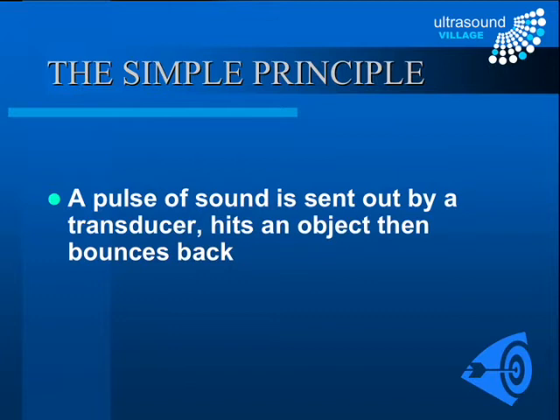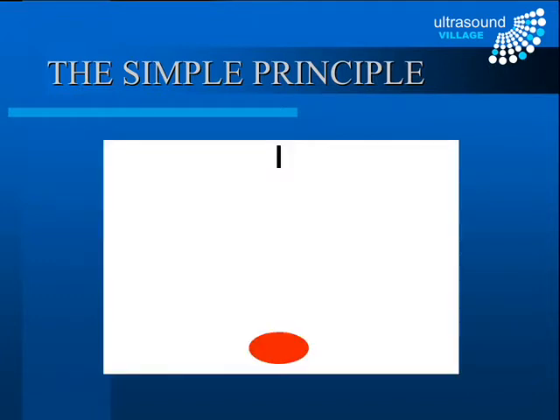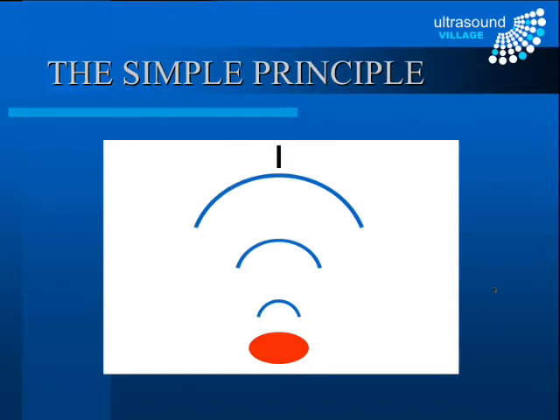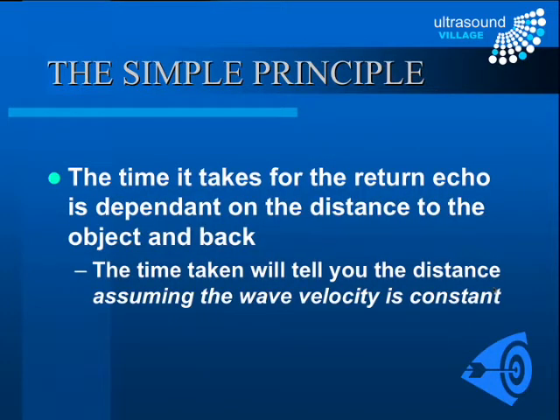At its most basic level, how does an ultrasound machine work? A pulse of sound is sent out by a transducer, it hits an object and bounces back. The time it takes for the return echo is dependent on the distance to the object and back. Assuming the wave velocity is constant, if we know that time and the velocity, we can calculate the distance between the transducer and the object.